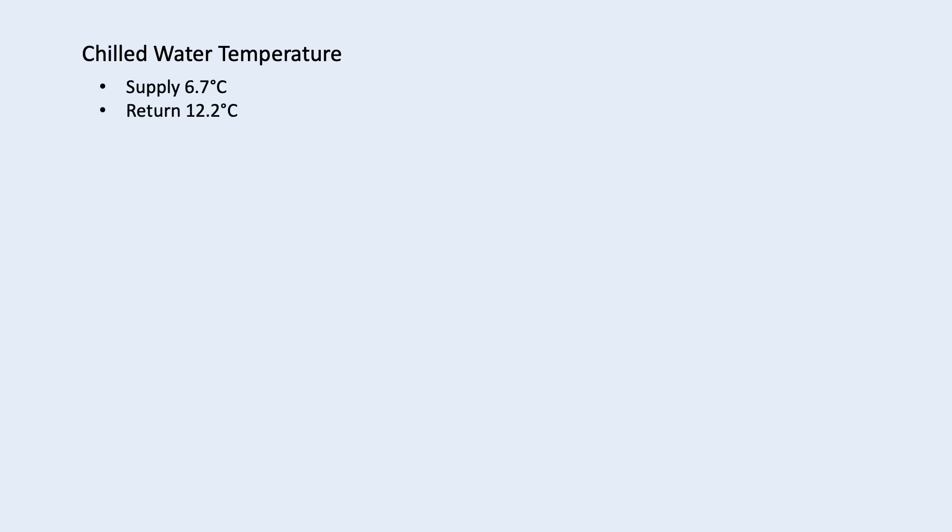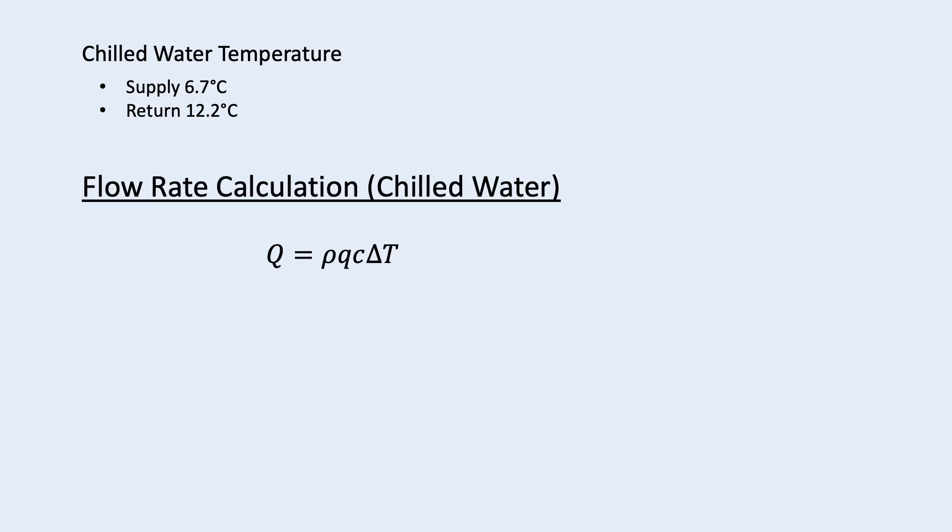For chilled water, the typical supply temperature is 6.7 degrees Celsius and the return is 12.2. With that, we can calculate the chilled water flow rate.